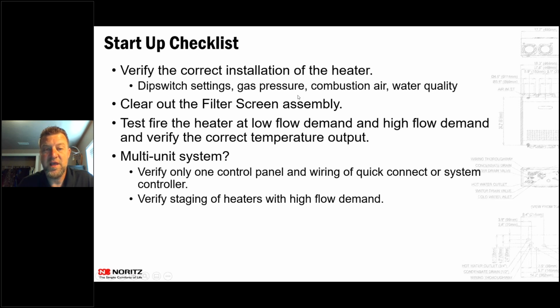Gas pressure: make sure you have enough gas and that the gas pressure is actually correct. With our units, with natural gas, it's 3.5 inches water column to 10.5 inches water column that is the working pressure, which you're going to find everywhere here in Utah. With propane, it's going to be 8 inches to 14 inches water column. So if you are doing a propane install, it's always a good thing to check to see if that inches of water column is below 14. I've seen a lot of propane districts where they're above 14, where they're 15 or 16 inches water column. If the gas pressure is too high, the unit's just not going to light, or it'll light and go right out. Same thing if it's too low, it'll light and then go straight out.